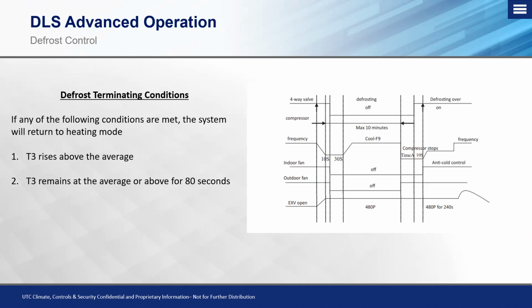However, if it's gone through multiple defrosts and it's struggling to heat the space, that's when we will consider that an unsuccessful defrost. And then we need to start looking at multiple factors, whether we're dealing with a sensor-based issue, whether we're dealing with an application issue, or the most common one, a charge-related issue, where we just can't get that outdoor coil hot enough because of the lack of refrigerant.